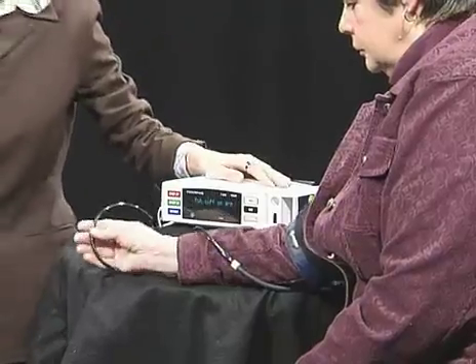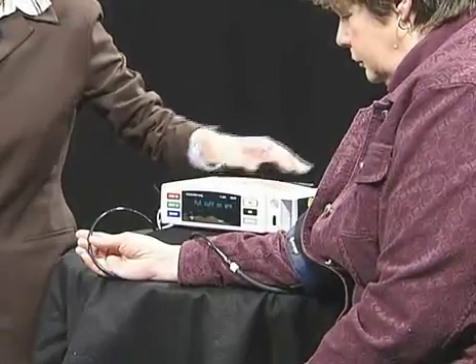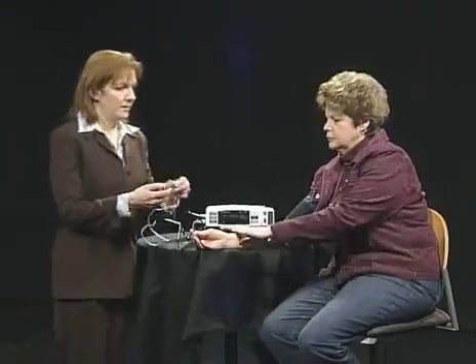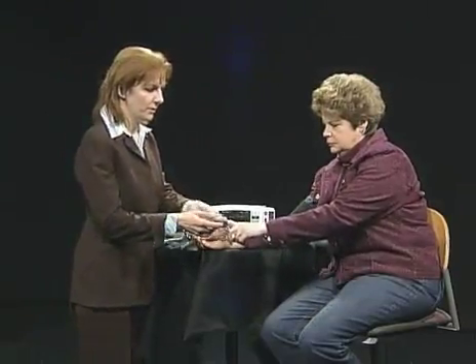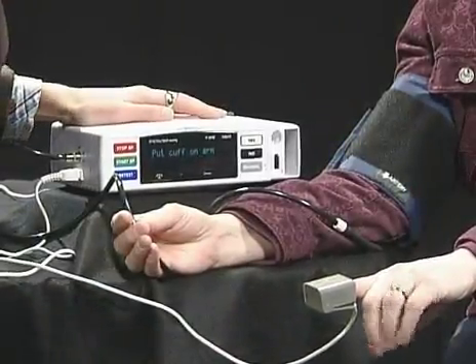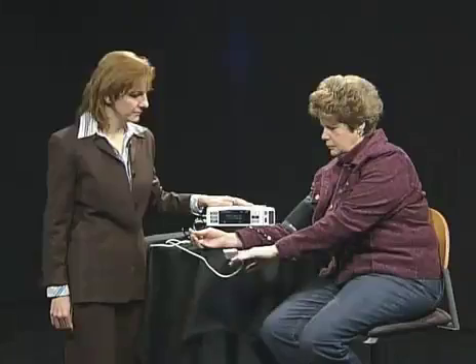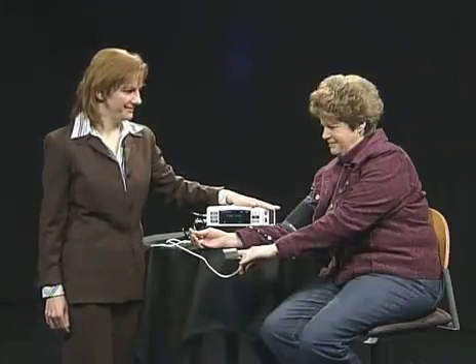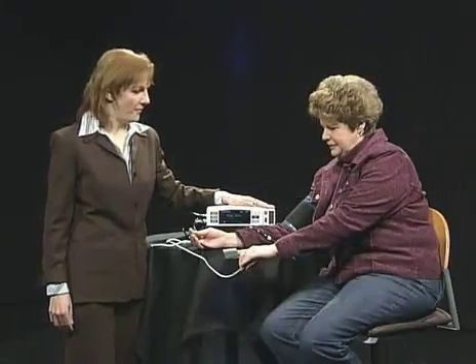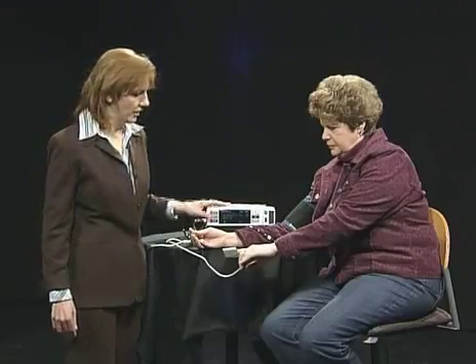The device instructs: "Take the blood pressure cuff on your right arm, above the elbow. Tighten it securely." A caretaker can help with this if needed. Next, we have the finger probe — it goes on their finger just like that. Once everything is on, the device says: "Rest your arm as instructed by your clinician." We tell them to rest their arm at heart level without bending their elbow, then hit the Start BP button.